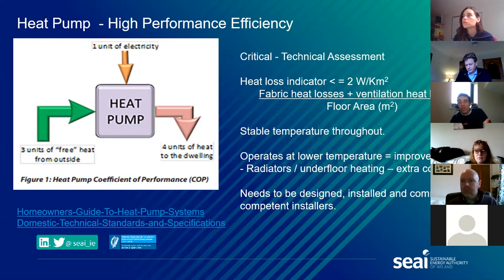So unlike a boiler, the heat pump is ready to provide heat continuously, so there's no clicking on and off like on a traditional boiler. Rooms are set at particular temperatures, be it 18 degrees for a downstairs room or 21 in bedrooms or so. When the temperature in those rooms goes below those degrees, it'll call heat from the heat pump. So with that in mind, it's critical that the heat loss indicator, the heat loss to the fabric and ventilation, is kept at a minimum, because we don't want the heat pump running continuously.